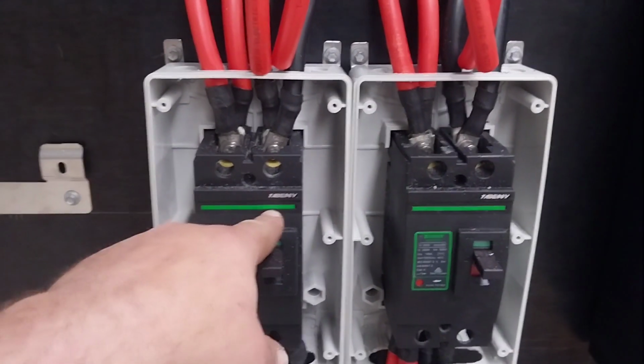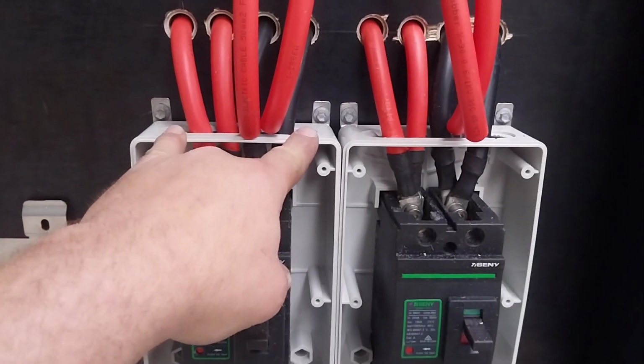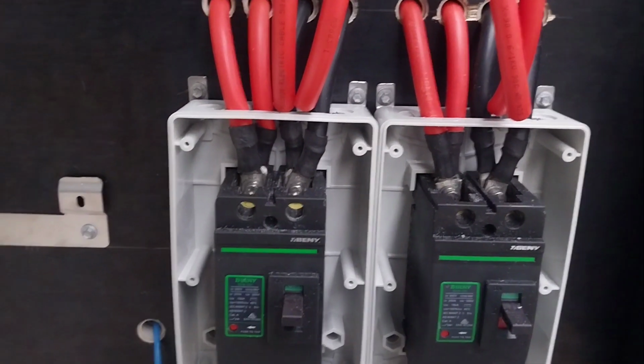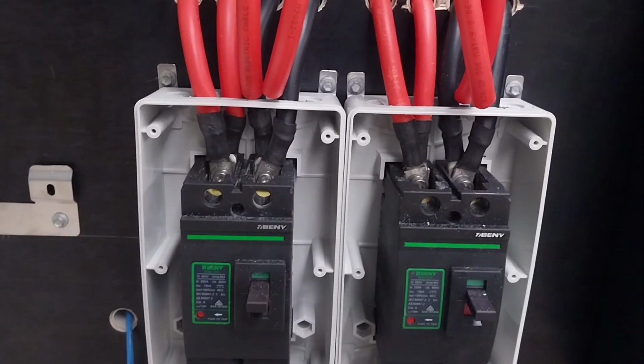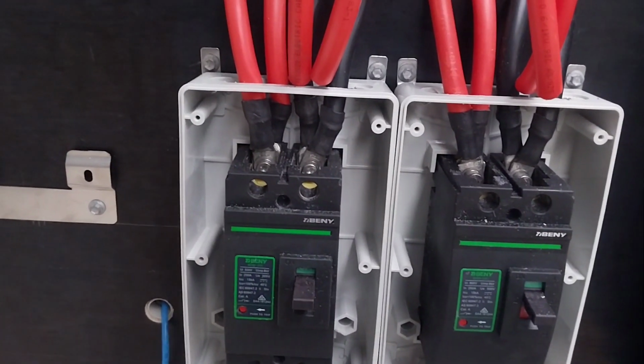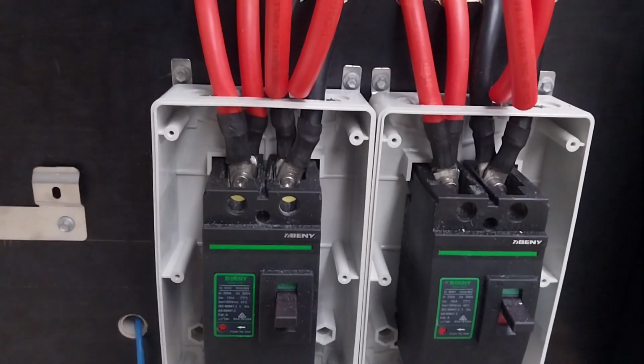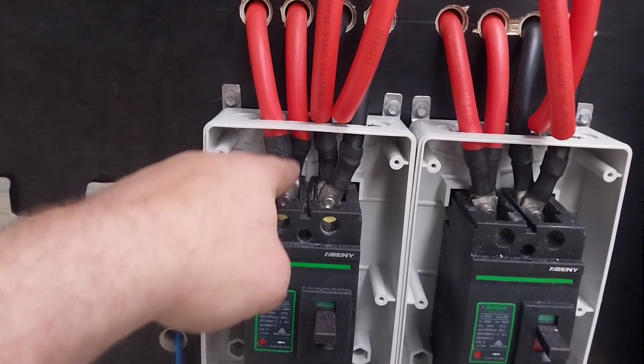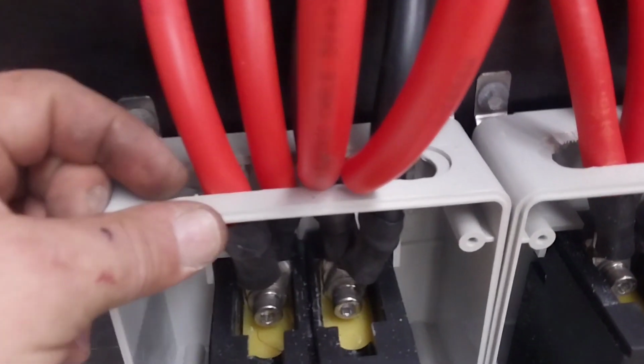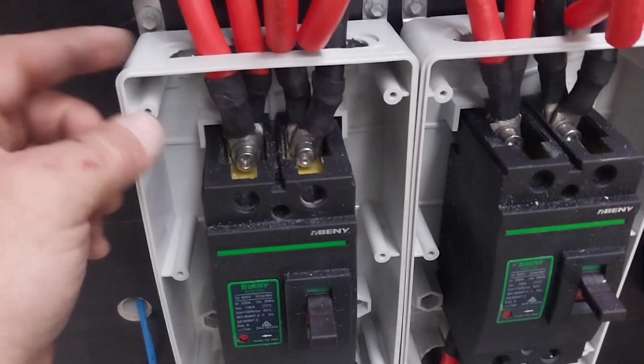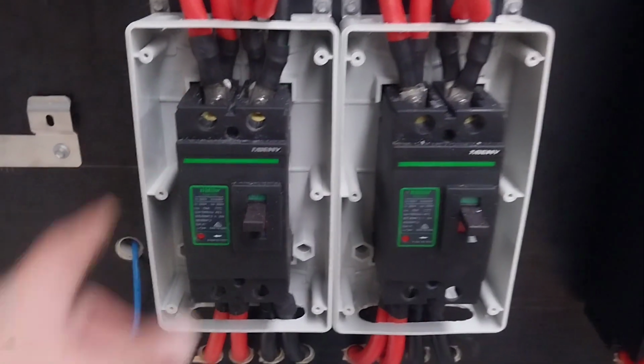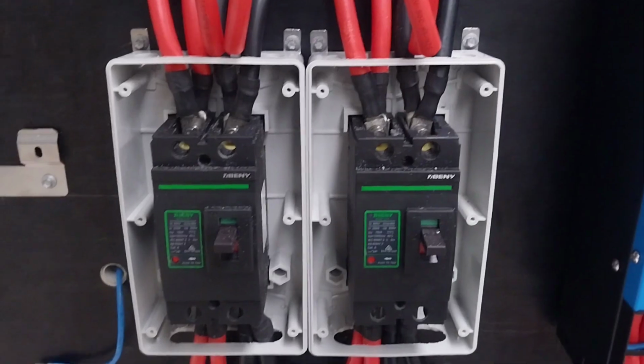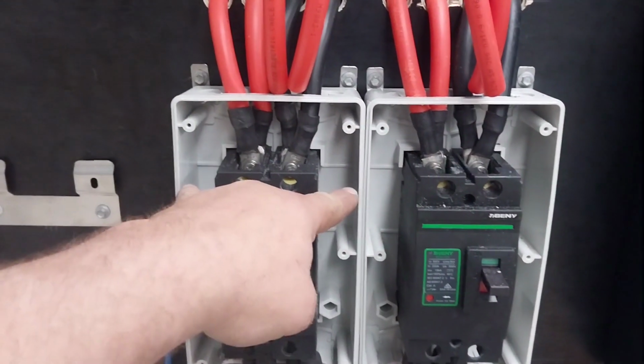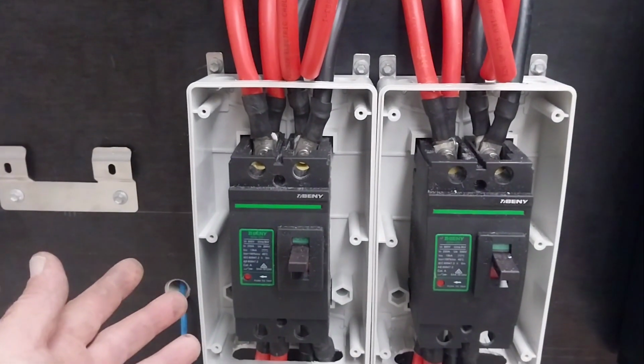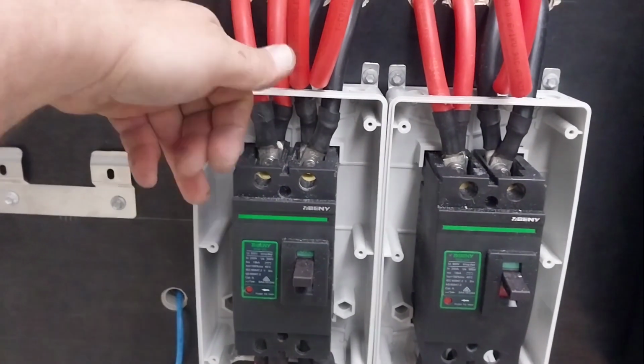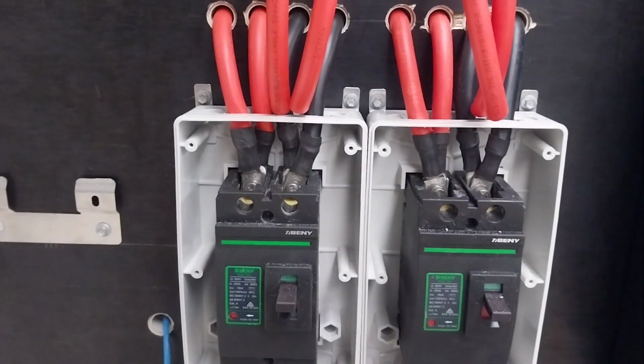Another problem is a two-pole circuit breaker in these boxes. Big no. Need to have a bigger box. This was very tight and they all have to converge into one terminal. I could have gone in line, but then the box thickness was only so much and all the holes were across, so these boxes are a bad idea. A better idea would be a four-pole breaker, 125 amp maybe, and run them in parallel in there.